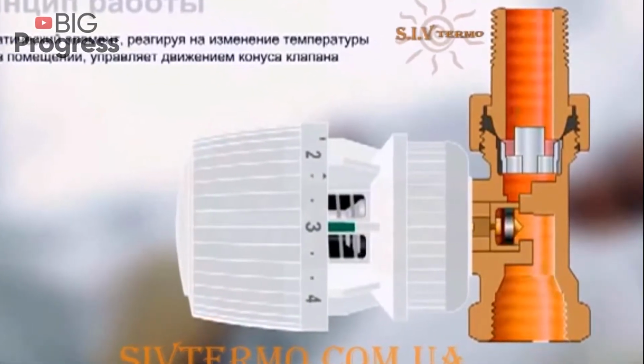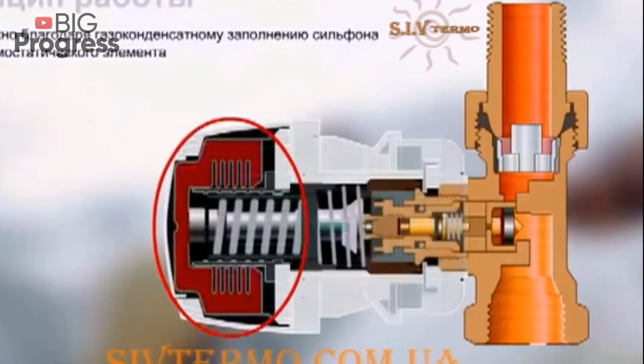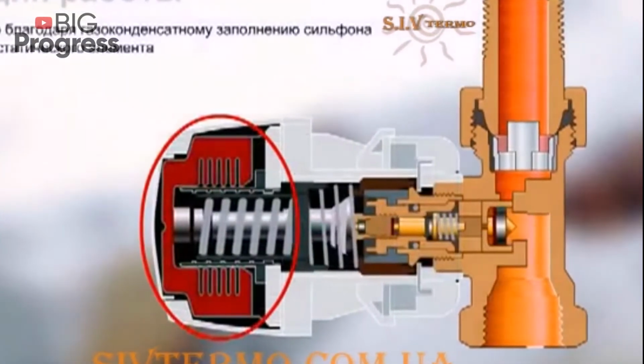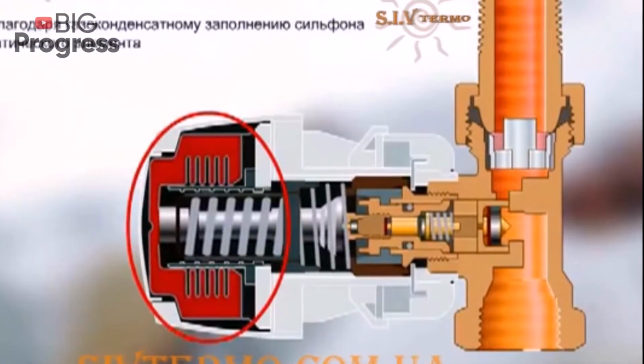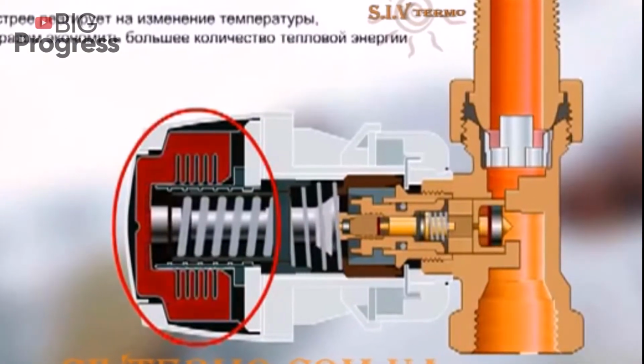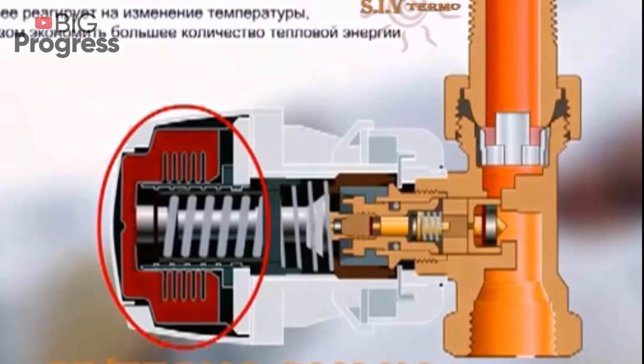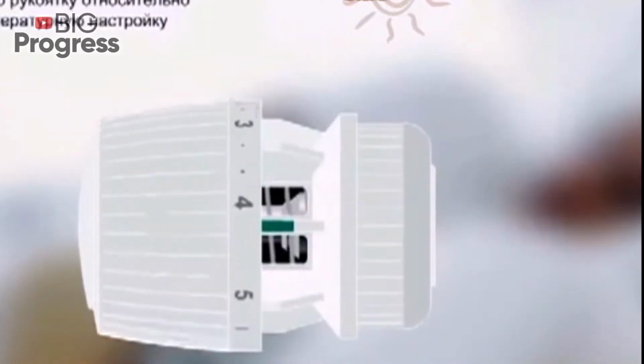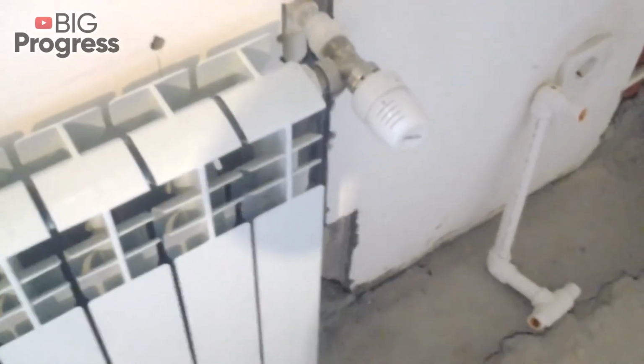When the air temperature in the room drops, the reverse process occurs. The bellows decrease in volume. The stem and cone of the thermostatic valve rise upward under the action of the spring. The amount of coolant increases, and the heat transfer of the radiator increases accordingly. Thus, the thermal head automatically maintains the required room temperature.